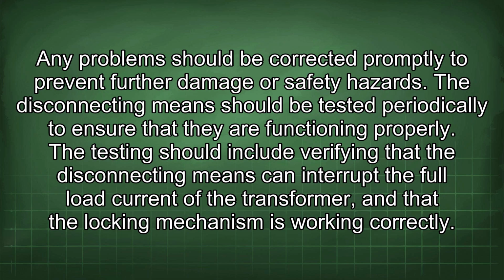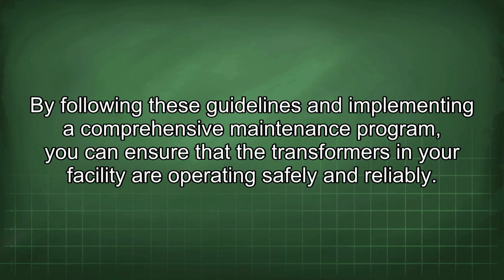The disconnecting means should be tested periodically to ensure that they are functioning properly. The testing should include verifying that the disconnecting means can interrupt the full load current of the transformer and that the locking mechanism is working correctly. By following these guidelines and implementing a comprehensive maintenance program, you can ensure that the transformers in your facility are operating safely and reliably.